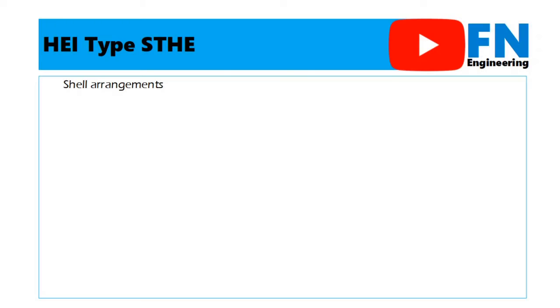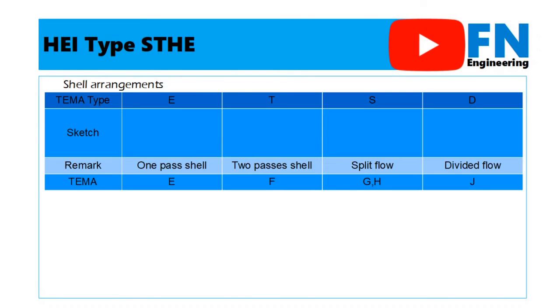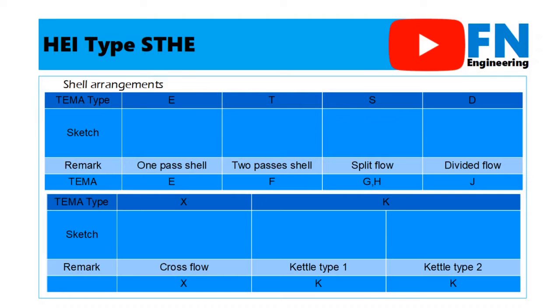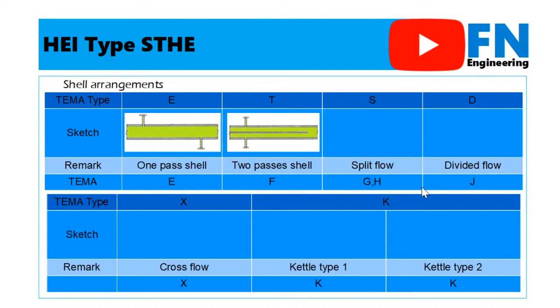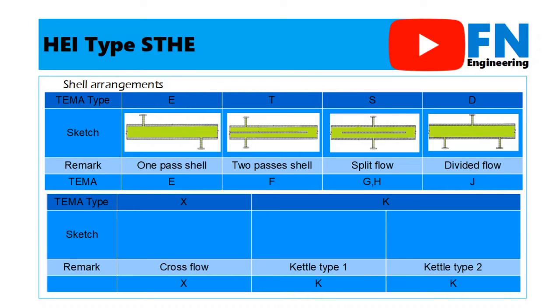The next arrangement is shell arrangements. There are 6 types for the shell. The first type is type E for one pass shell. It is also type E in the TEMA standard. Then type T is for 2 passes shell, or type F in the TEMA standard. Split flow is identified by type S. It is similar to type G or H in the TEMA standard. Then type D is for divided flow, or similar to type J in the TEMA standard.